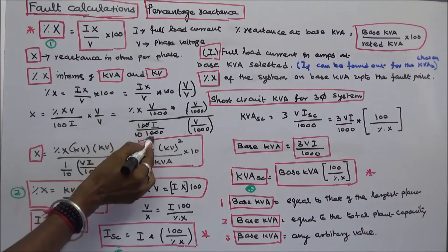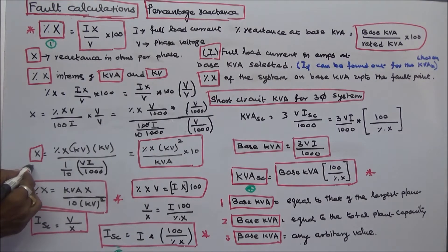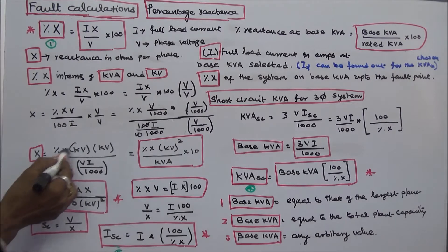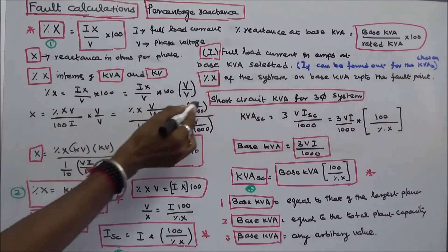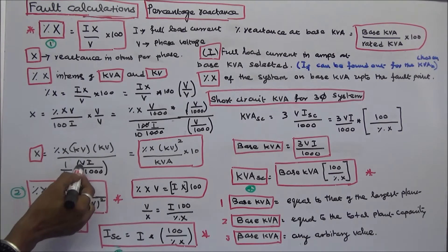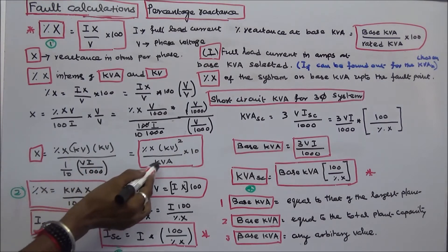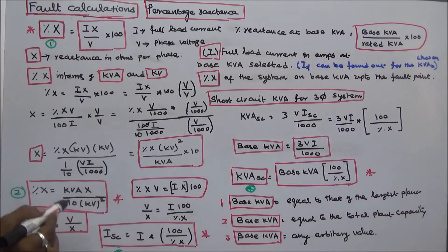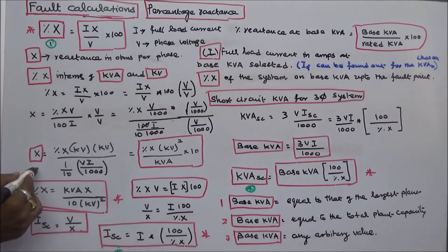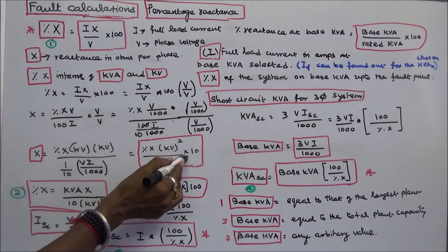Since 100 divided by 1000 equals 1 over 10, reactance in ohms per phase equals percentage X times KV times KV divided by 10 times KVA. Therefore, X equals percentage X times KV squared divided by KVA times 10, and percentage reactance equals KVA times X divided by 10 times KV squared.